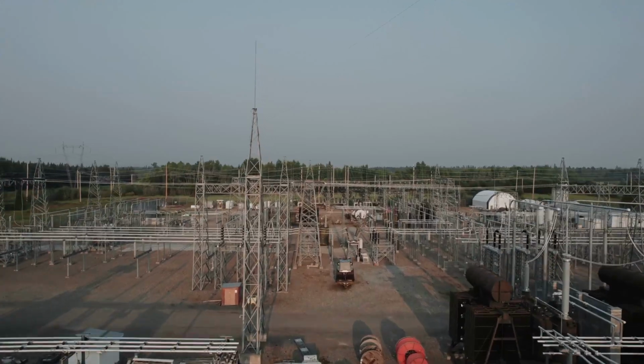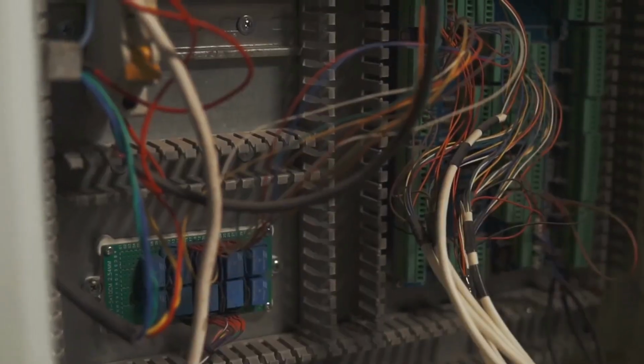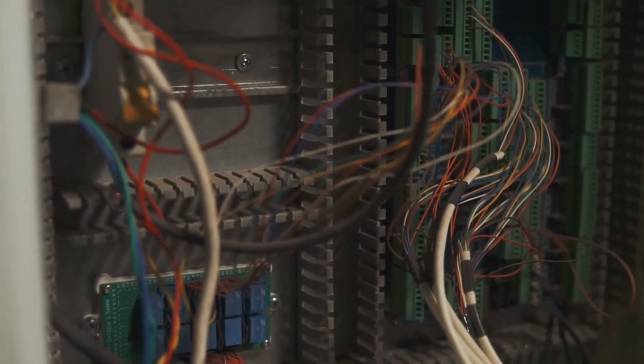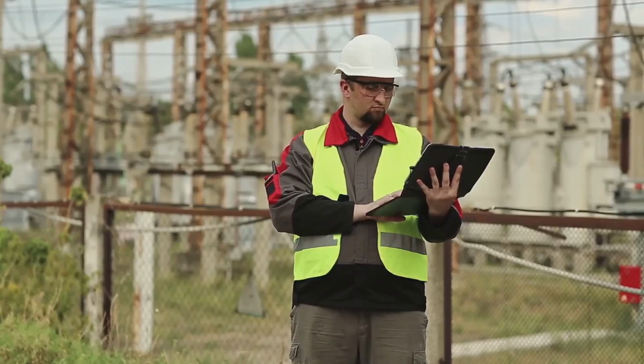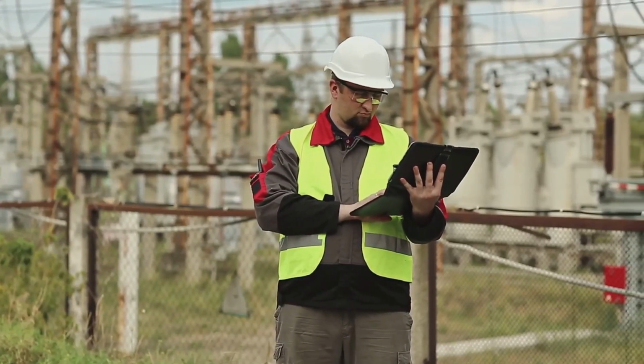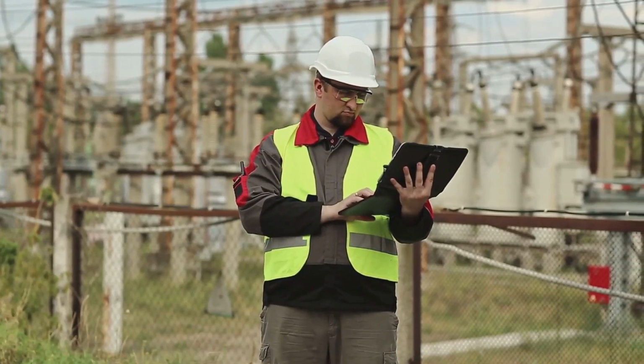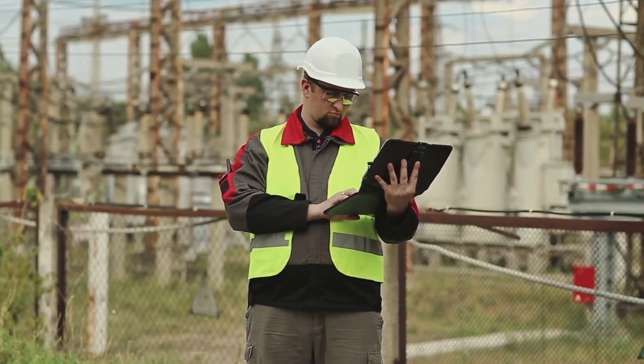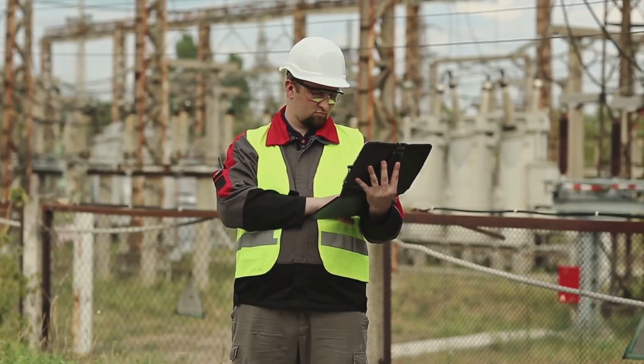Clause 4.8 Grounding coordination. Proper grounding is key to ensuring safe and reliable DER operation. In the context of FRT, a grounded DER helps ensure accurate fault detection and contributes to system stability during asymmetrical faults like single line-to-ground events.